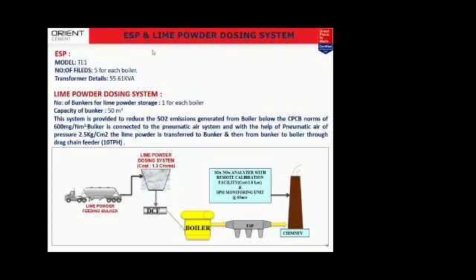For controlling SO2, we have a lime powder dosing bunker installed in our boiler. Each boiler has a lime powder dosing system bunker, which has a capacity of 50 meter cube. We invested around 1.3 crores initially, right from the beginning of the plant, and we have incorporated it.